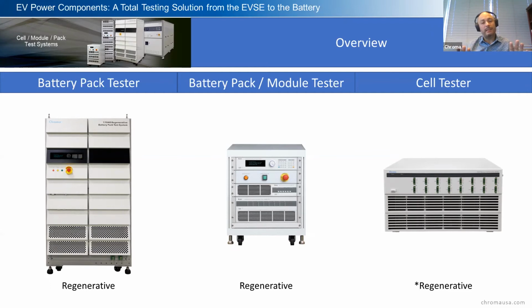For the module and cell testers, those are multi-channel. The pack testers are typically 1 or 2 channel. One technology we have on all our battery testers and simulators is that if you're charging on one channel and discharging on another, instead of taking power from the grid and putting it back to the grid, we cycle power from one channel to another, say from channel 1 to channel 2. If both channels are charging, we take power from the grid. If both are discharging, they go back onto the grid, or they loop from channel to channel. This happens automatically during your test or simulation.